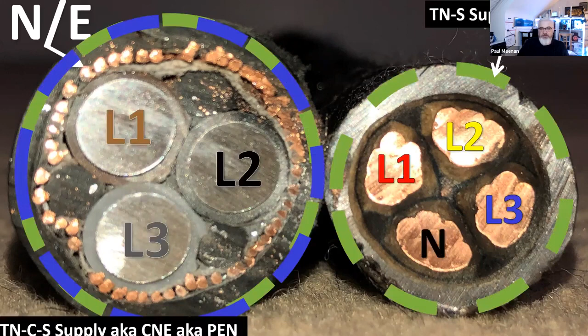Yeah, we've got two examples of cables here basically just cut through so you can see what's inside. This is the sort of stuff that would supply a property. If these are 3-phase cables, but they're also used for single - you just tap off one of the phases and the other. So on the right there, we've got the older type, which has got copper conductors, and you've got 4 conductors inside. You've got your three phases, L1, L2, and L3, and the neutral, all separate, insulated individually. Around the outside of that, we've got the outer, which is going to be earth, usually lead or something in the case of that one.